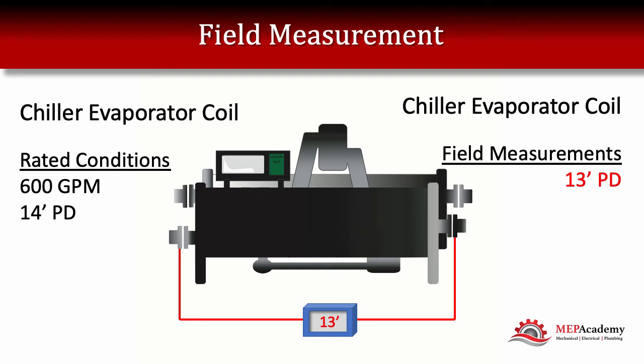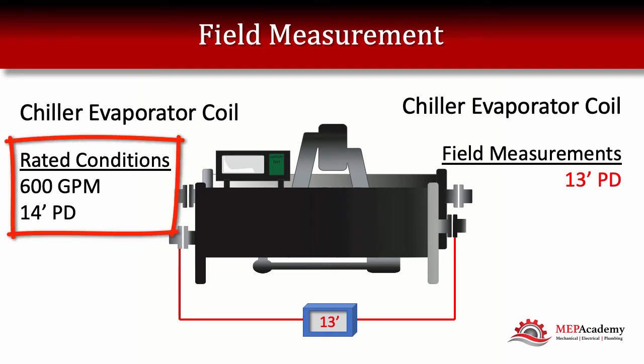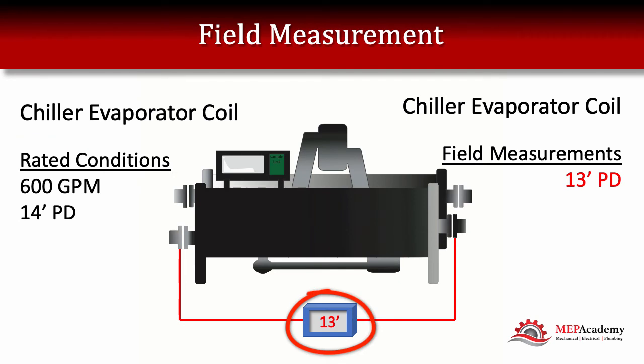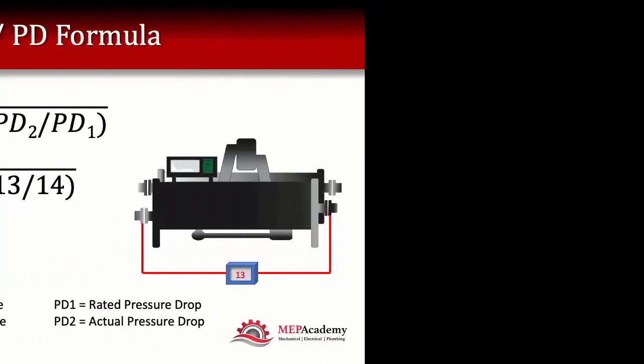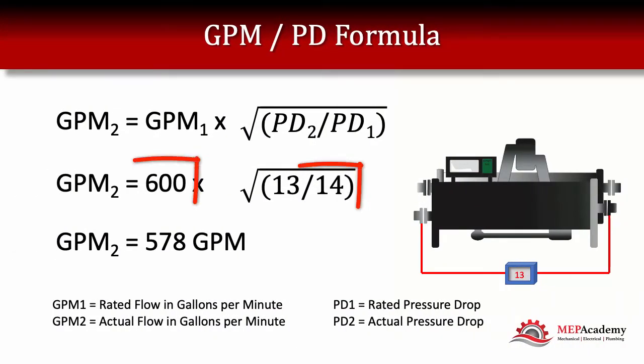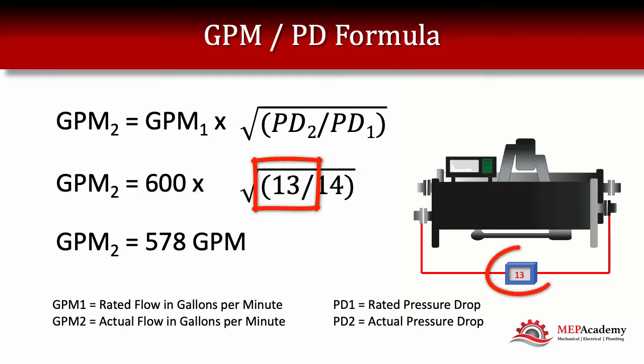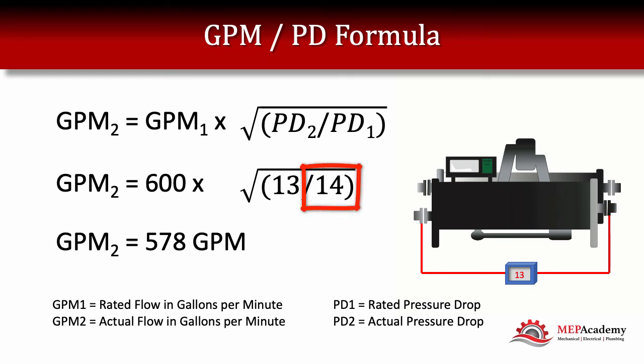We're going to take all the known rated conditions of the new piece of equipment — in this example, the evaporator of a chiller — and the actual measured pressure drop from the field technician. Here's our formula: all we're going to do is put in the known rated values for the evaporator, which is GPM1. The rated GPM is 600 times the square root of the actual measured pressure drop, which came out to be 13 feet, divided by the rated pressure drop of 14 feet for our example evaporator.